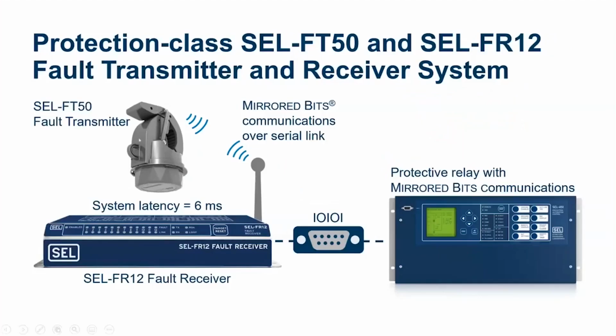This is my FT50, which is line powered. As long as you have more than 5 amps of load current on your system, they basically power themselves up. They send the signal to this remote receiver called FR12. The FR12 can be connected to up to 12 transmitters. And this has a certain amount of line of sight range, but if you want to increase the range, SEL recently came up with a repeater called the RP50 repeater. So you can add repeaters if you want to increase the range between the FT50 and FR12.